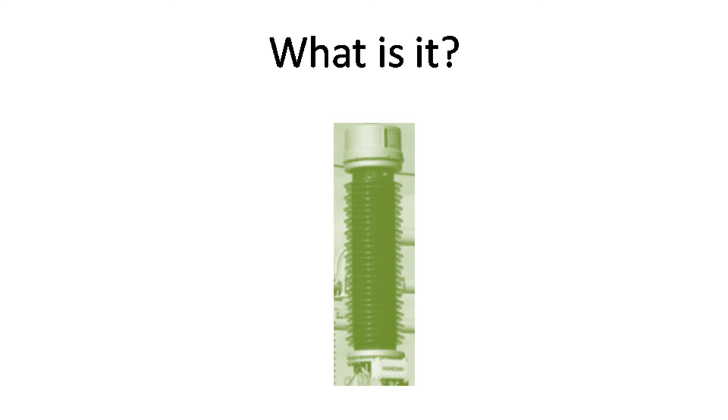You may also hear of capacitive voltage transformer. Well, what is the difference between having an inductive element versus the capacitive element voltage transformer? The structure is basically the same with an inductance winding or coil, but the capacitive has an additional voltage divider with capacitive elements. The additional capacitive voltage divider allows the size requirements to be smaller than inductive voltage transformers.